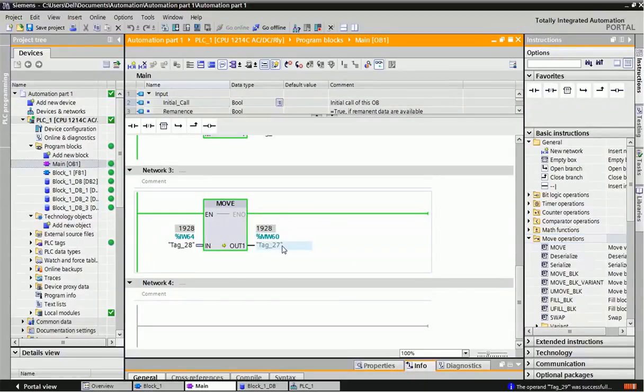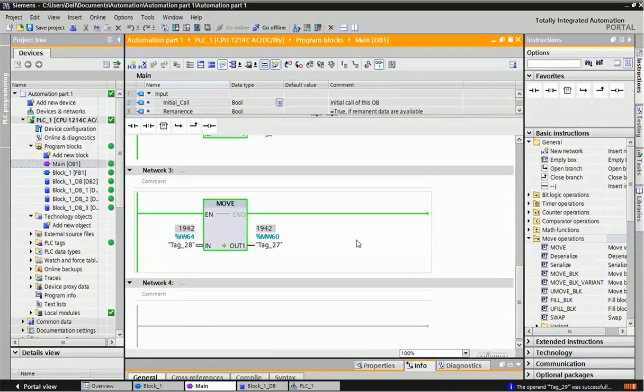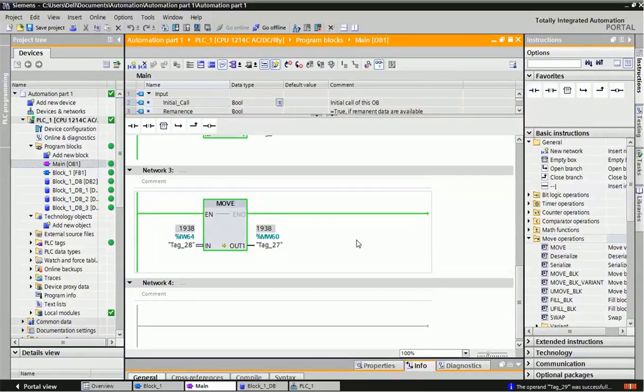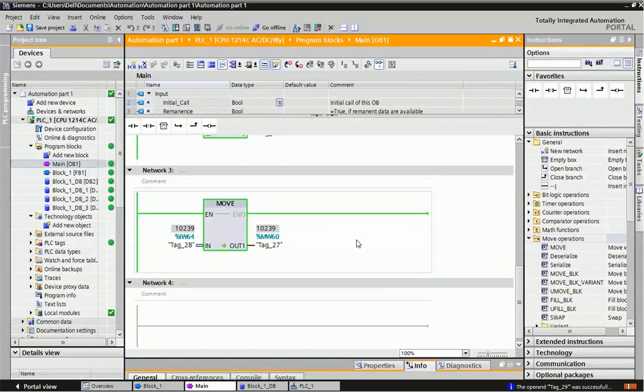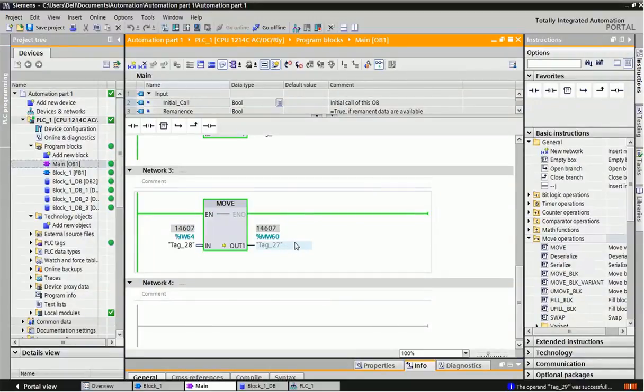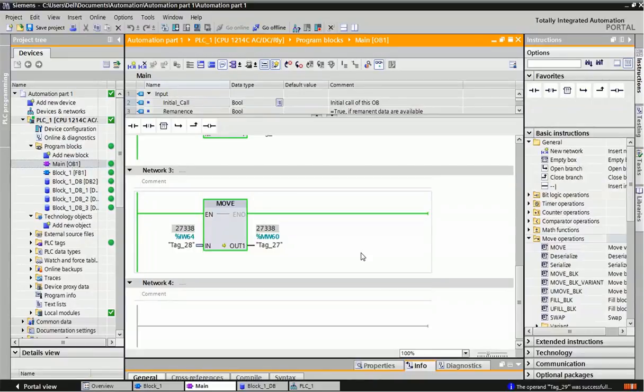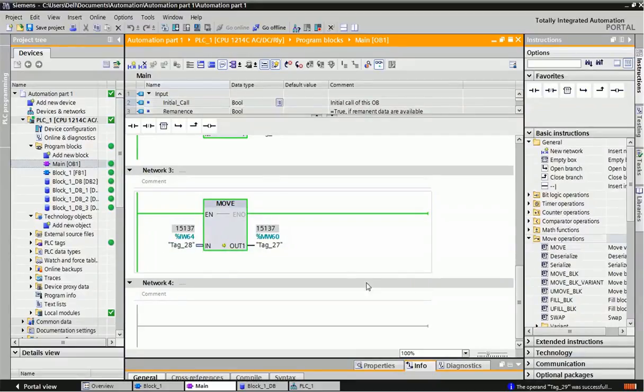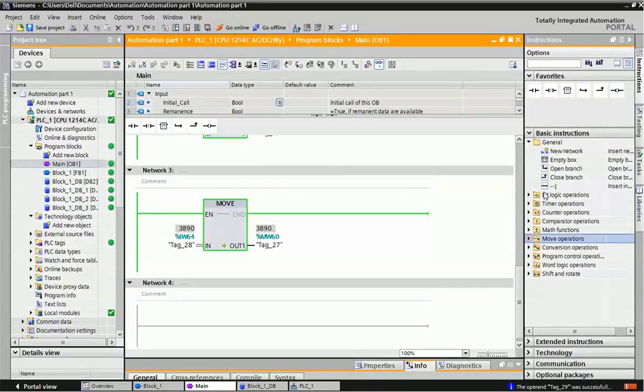Whatever signal is coming from analog will be moved into MW60. You can use this memory word in SCADA or any HMI systems to display the value. If you want to move any value into memory word or memory double word, display the value in SCADA HMI, or use it in another controller or for mathematical modeling, the move block is very useful for assigning values. When I increase the value at IW64, you can see the value is moved into MW60. This value we're getting without scaling, meaning we're getting the raw value. Because of 16-bit, this value is converted into decimal type.